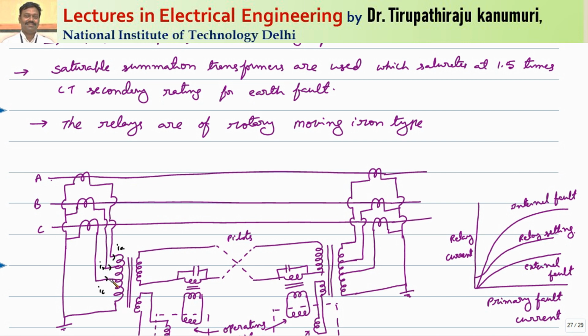And whenever there is a ground fault, because this is connected to neutral, the current passing through this one will be the sum IA plus IB plus IC. So this sum of the currents will pass through this one. This current will not be equal to 0 only for the case of ground faults. Accordingly the flux will be produced in this core, and that flux will link with the secondary.